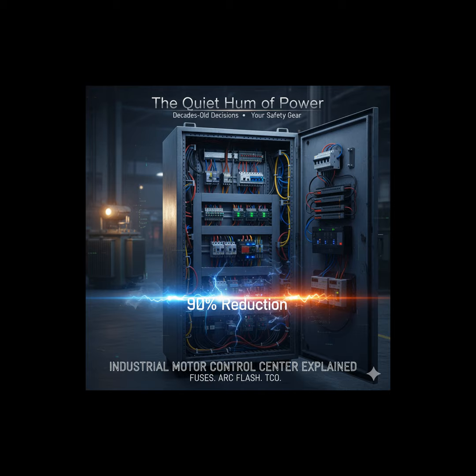Wow. Okay, now let's step back and look at the physical structure holding all this sensitive technology. These MCC cabinets have to survive the facility environment. They have to house massive copper buses and contain fault explosions. What regulatory framework governs their physical safety and construction? It's really a three-way partnership. You have UL, specifically UL 845, which tests the product design for overall safety. Can it contain a fault without exploding? That seems important. Very. Then NEMA sets the construction and performance ratings, establishing critical parameters like bus bar temperature rise. If the ambient temperature is 40 degrees Celsius, NEMA standards often limit the temperature rise of the bus to 65 degrees above that. So keeping those huge copper bars cool is paramount.